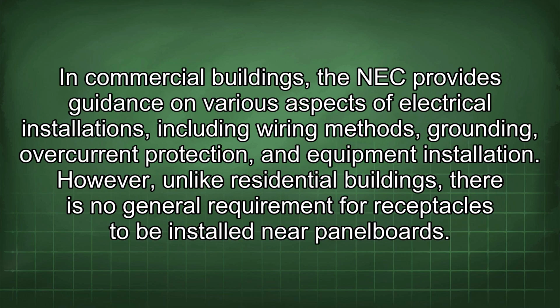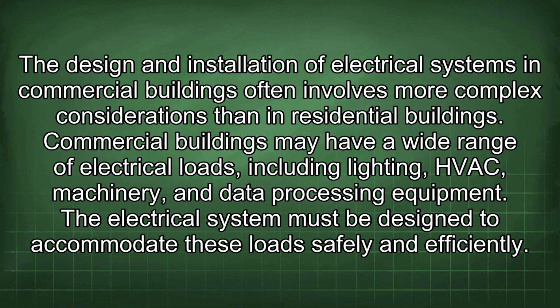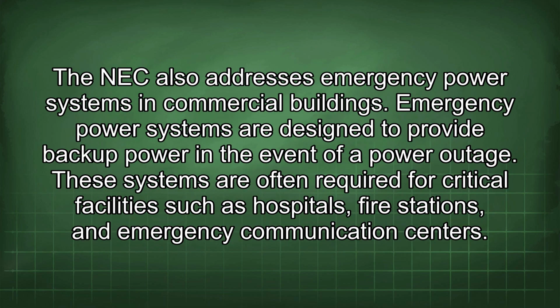In commercial buildings, the NEC provides guidance on various aspects of electrical installations, including wiring methods, grounding, overcurrent protection, and equipment installation. However, unlike residential buildings, there is no general requirement for receptacles to be installed near panel boards. The design and installation of electrical systems in commercial buildings often involves more complex considerations than in residential buildings. Commercial buildings may have a wide range of electrical loads, including lighting, HVAC, machinery, and data processing equipment. The electrical system must be designed to accommodate these loads safely and efficiently. The NEC also addresses emergency power systems in commercial buildings.